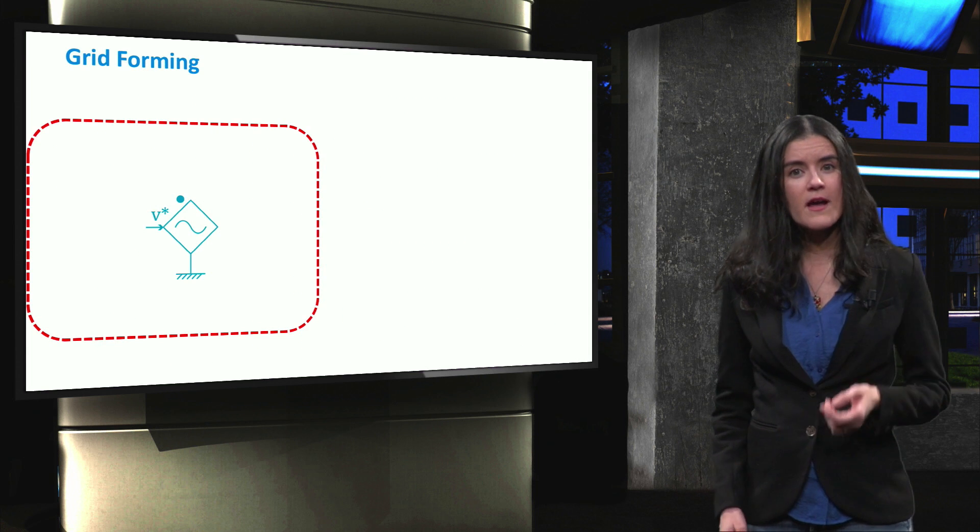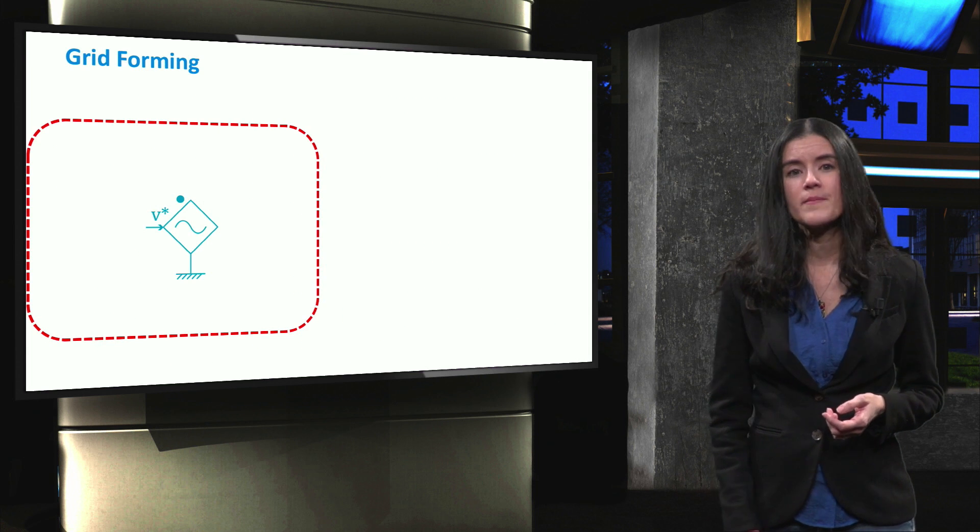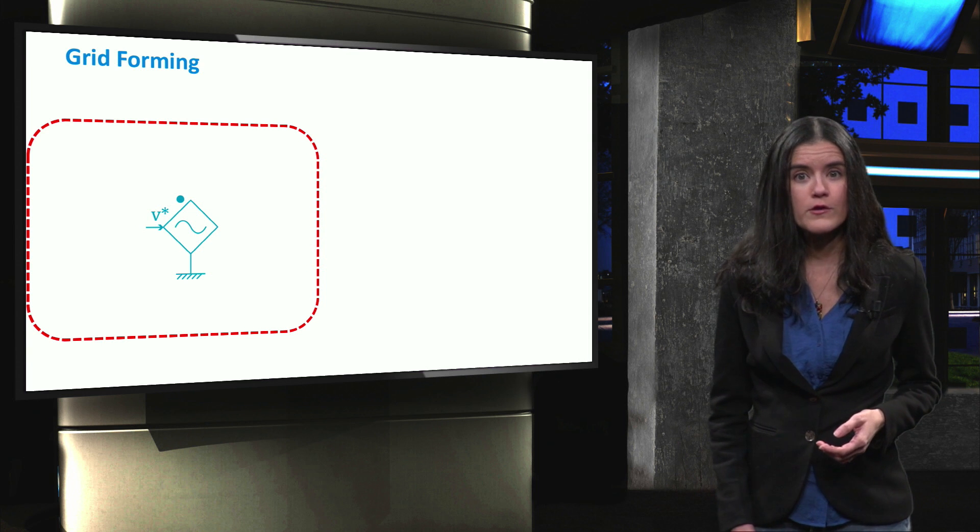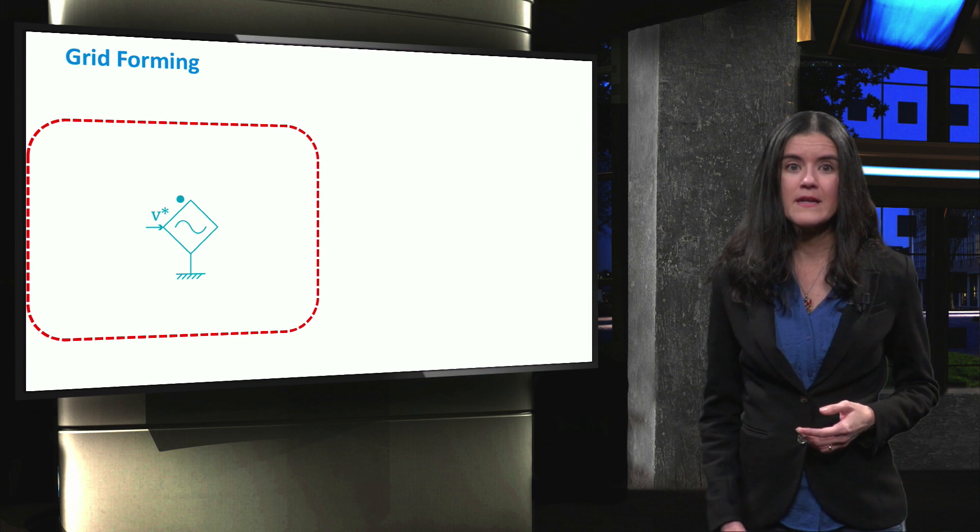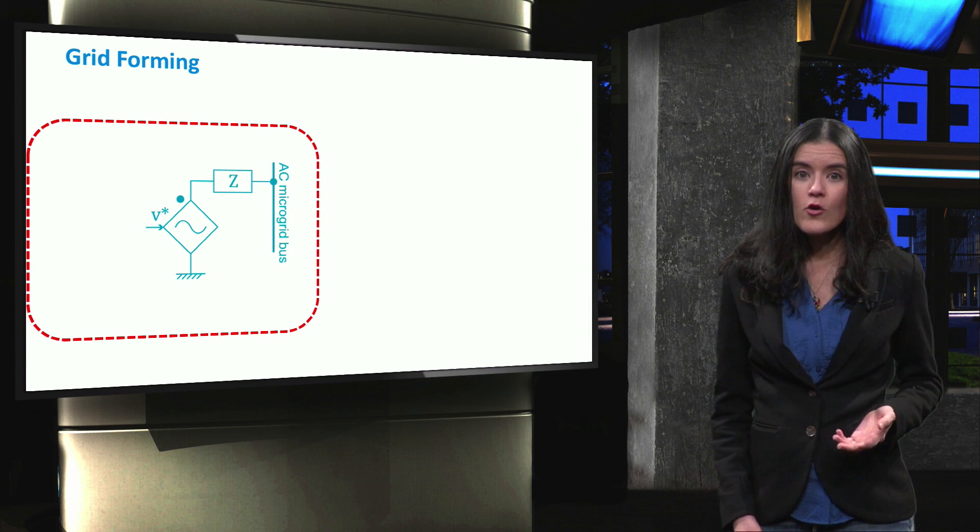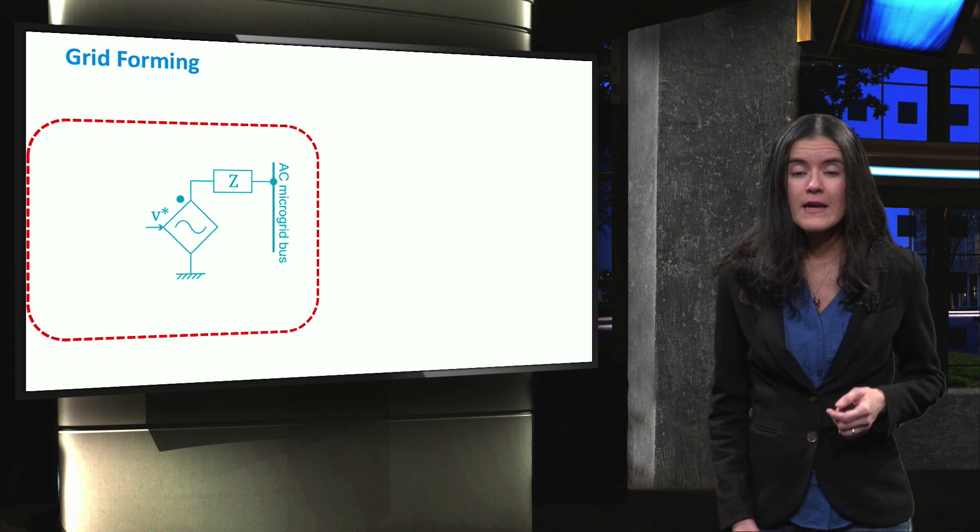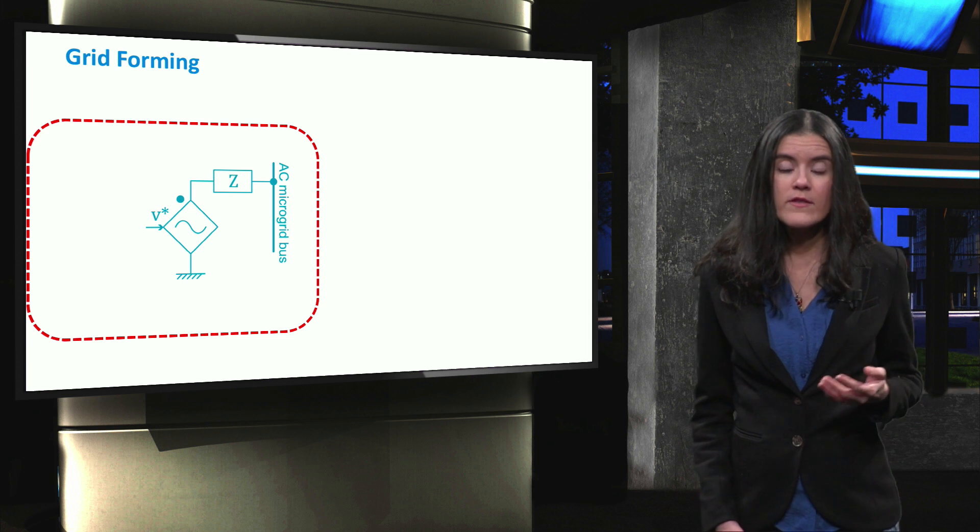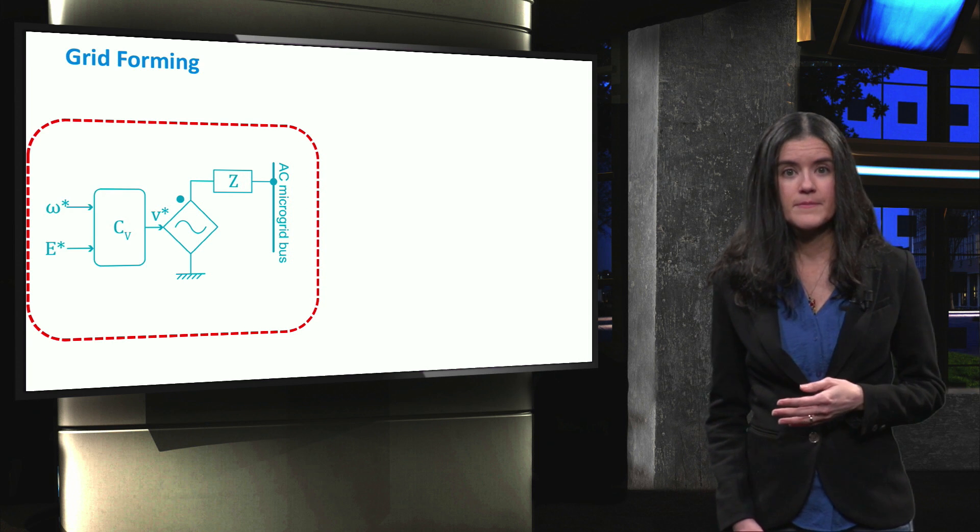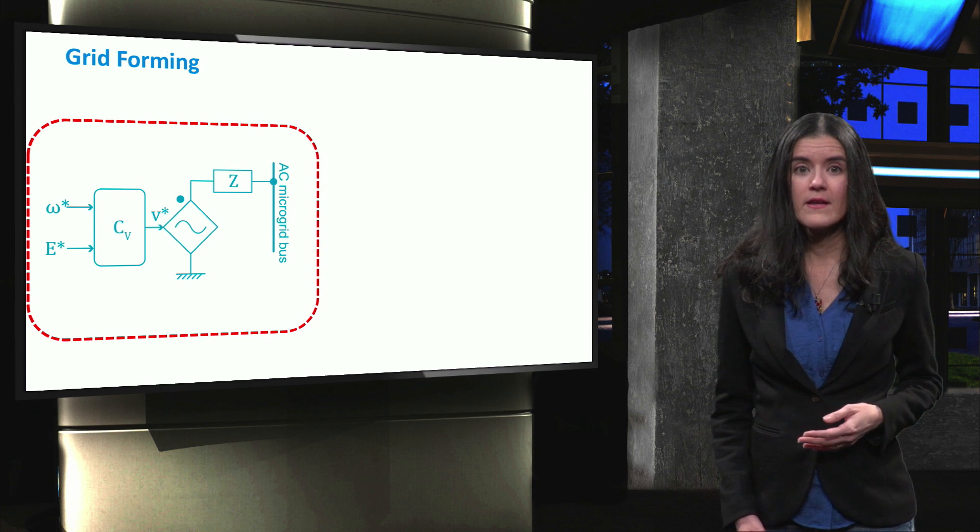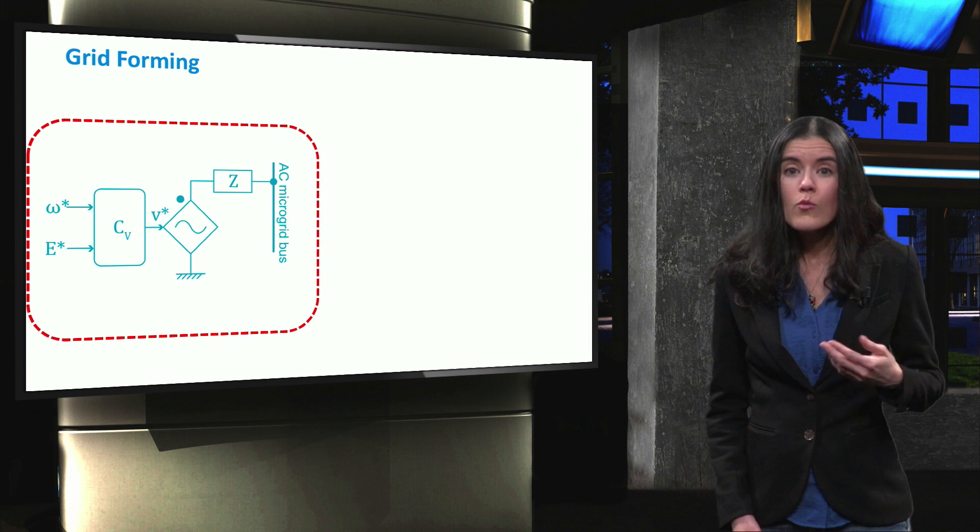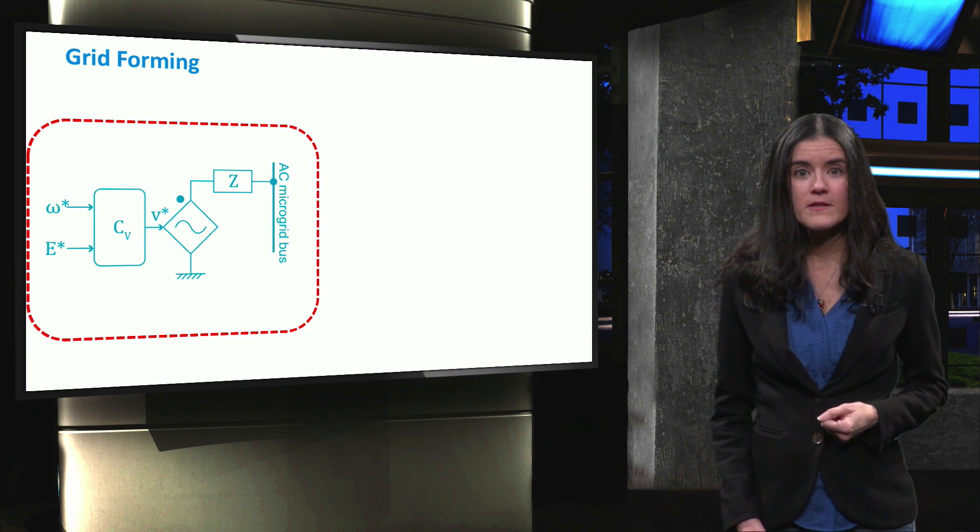So let's first have a look at the grid-forming type. A grid-forming converter can be represented by an ideal AC voltage source with low output impedance. The main goal of a grid-forming converter is to form a stable grid with constant voltage and frequency. For this reason, these converters can only operate in islanded mode, where voltage and frequency is determined by them.